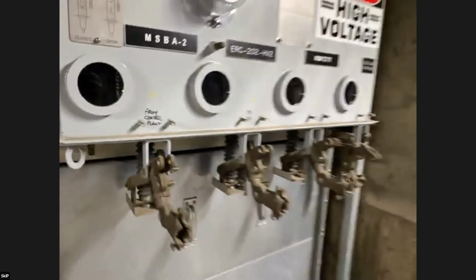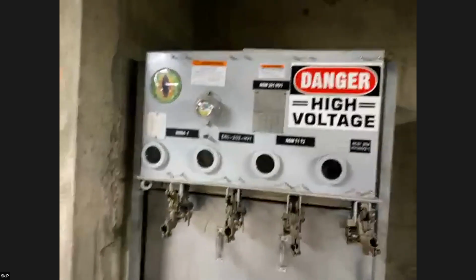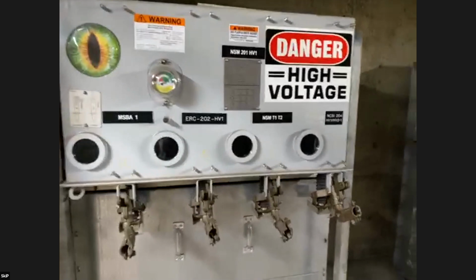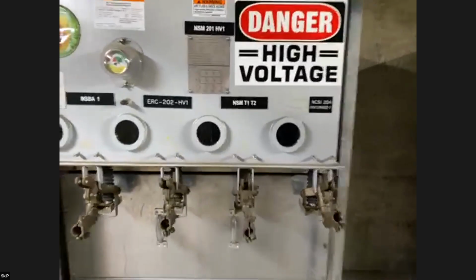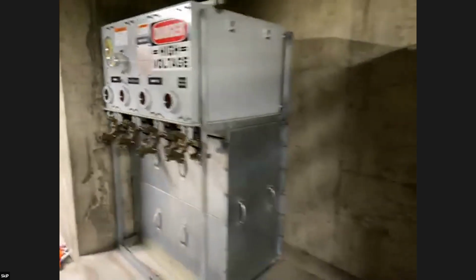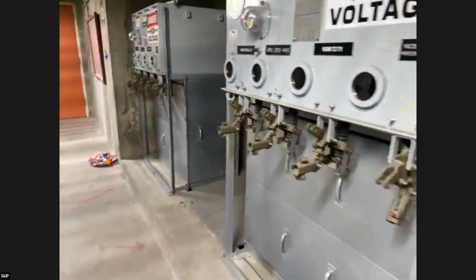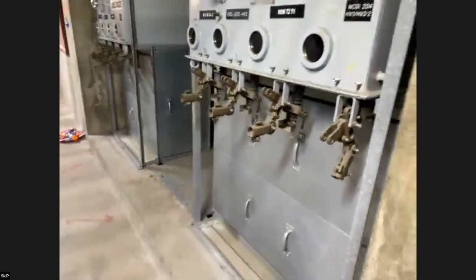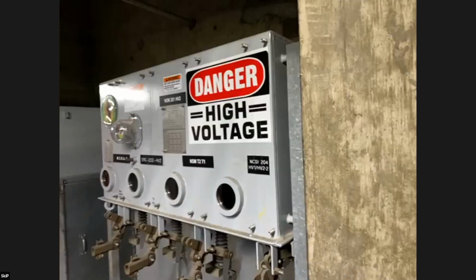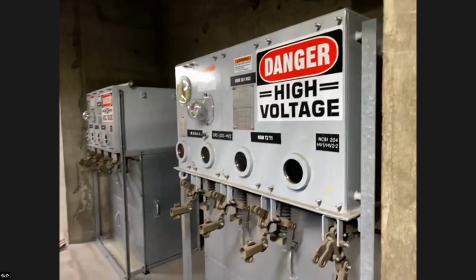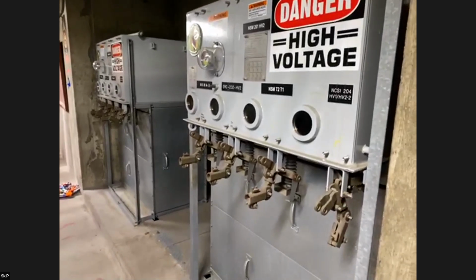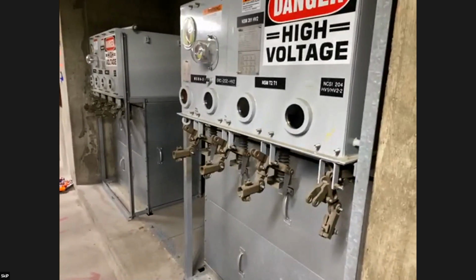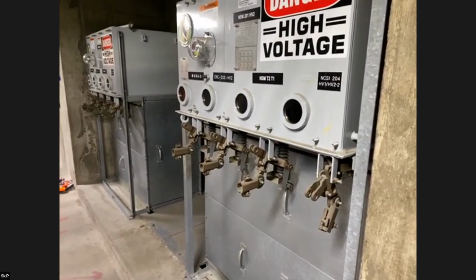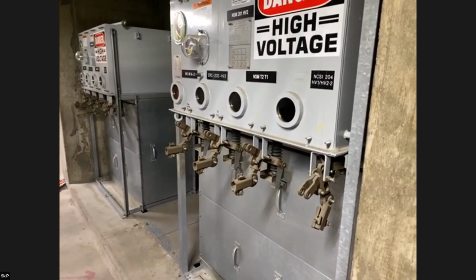We have to do something so that it doesn't explode, because 12,000 volts with oxygen and fuel makes a big bomb. So these things are full of an inert gas that makes it so there's no oxygen inside. What we just found out this year is that inert gas is one of the worst greenhouse gases for the ozone there is, worse than the refrigerants people talk about. So in the next couple of years we're going to be working on getting rid of these and going to a more modern, state-of-the-art system that doesn't use as bad a gas.